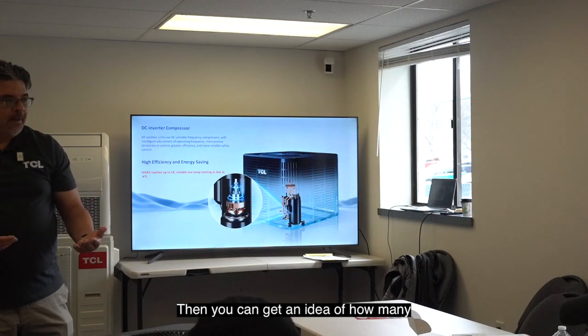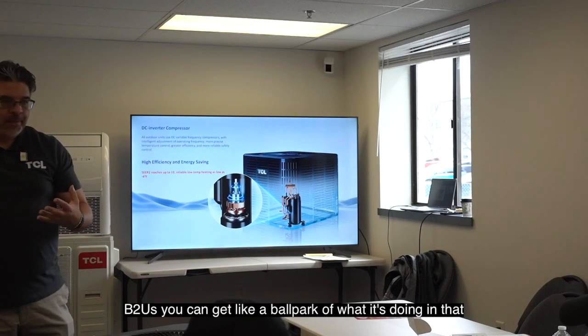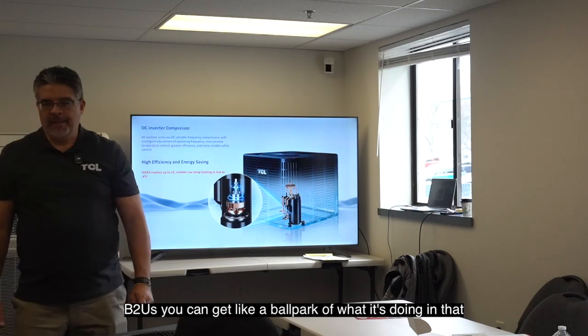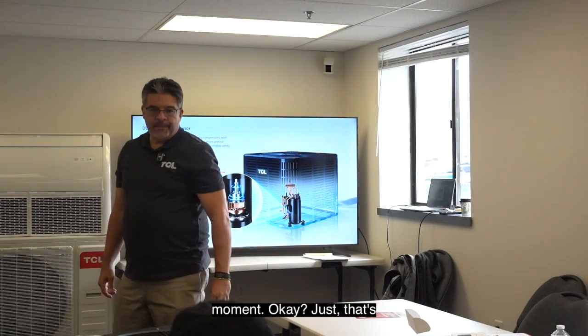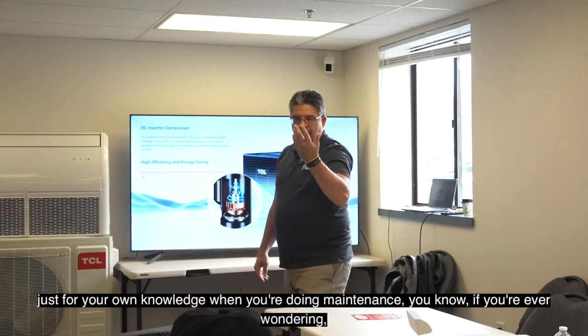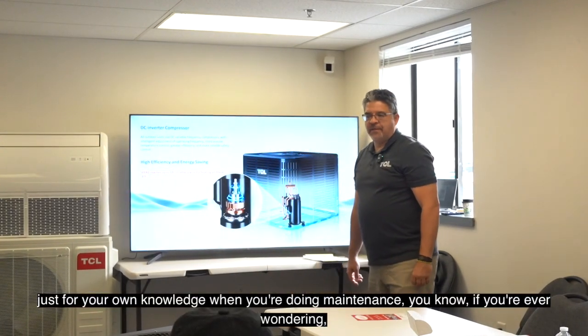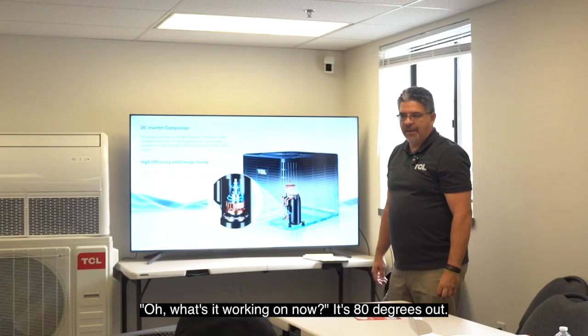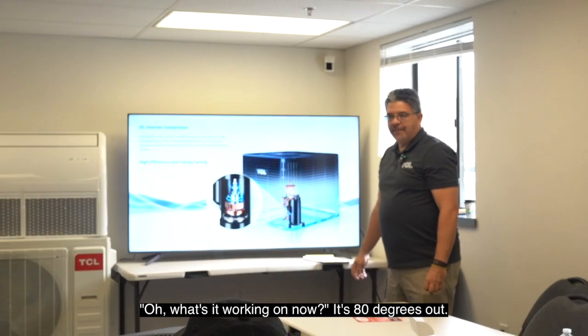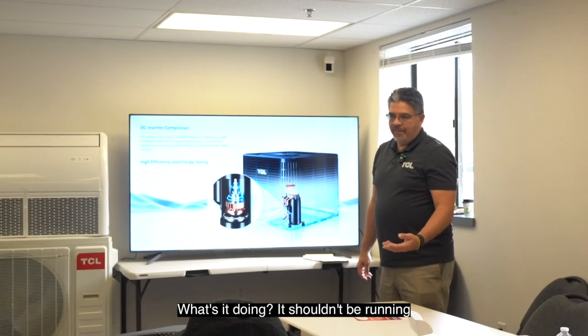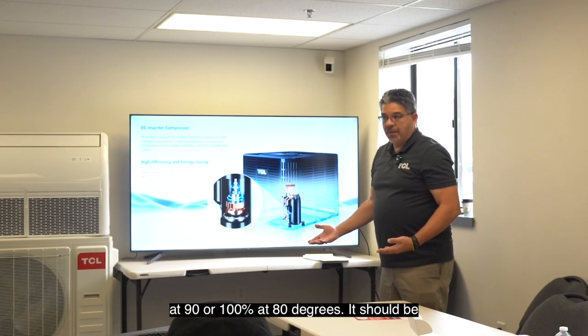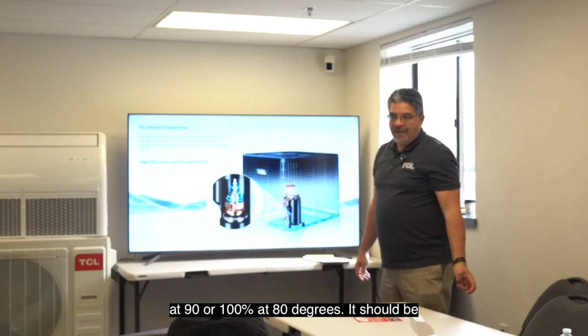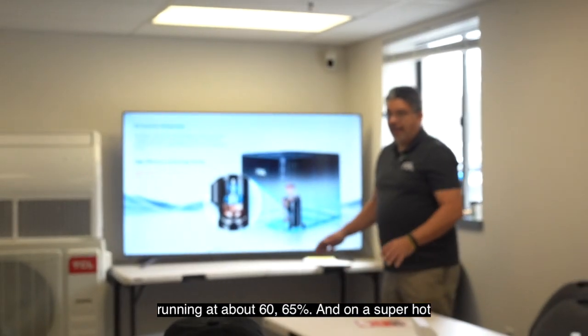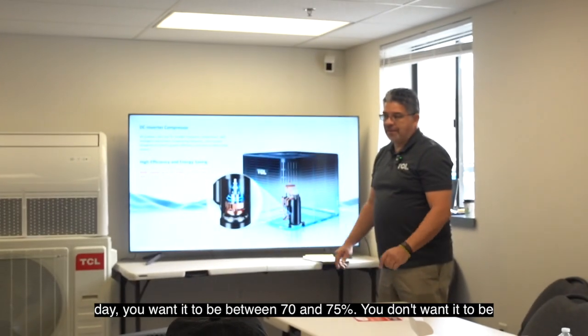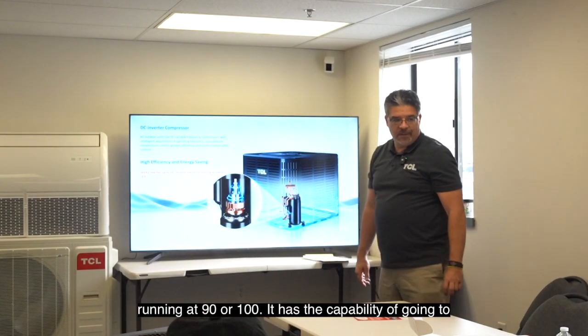Then you can get an idea of how many BTUs. You can get like a ballpark of what it's doing in that moment. Okay? That's just for your own knowledge when you're doing maintenance. If you're ever wondering, oh, what's it working at now? It's 80 degrees out. What's it doing? It shouldn't be running at 90 or 100% at 80 degrees. It should be running at about 60, 65%. And on a super hot day, you want it to be between 70 and 75%. You don't want it to be running at 90 or 100.